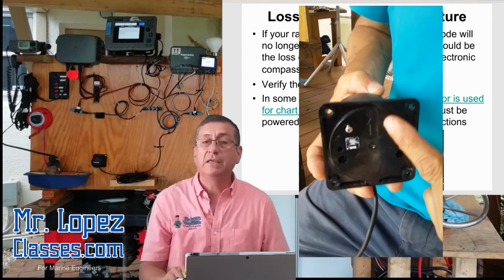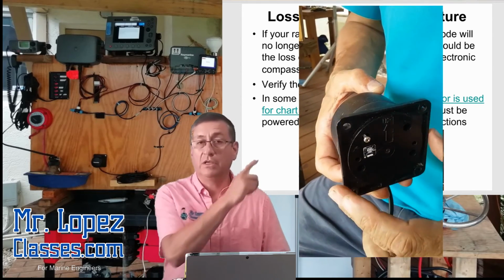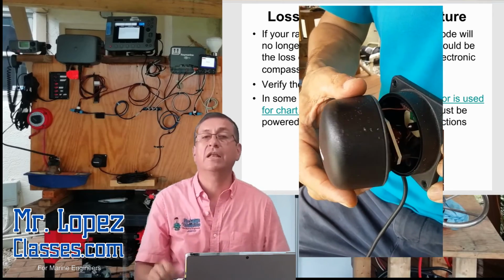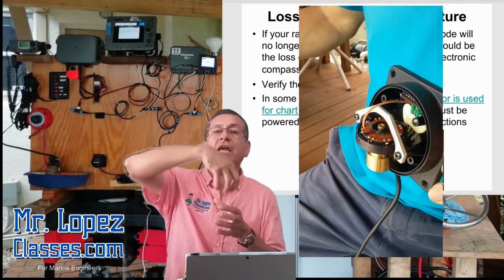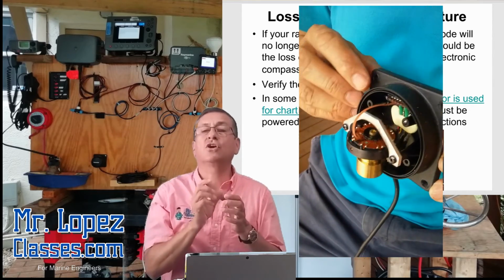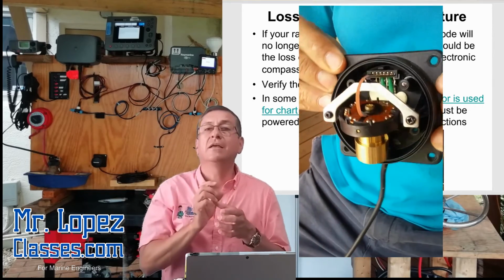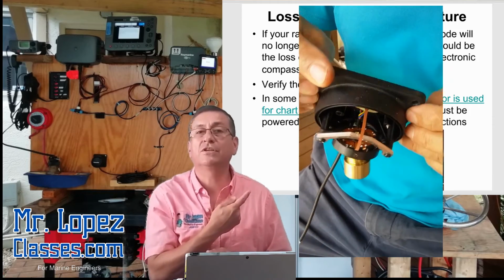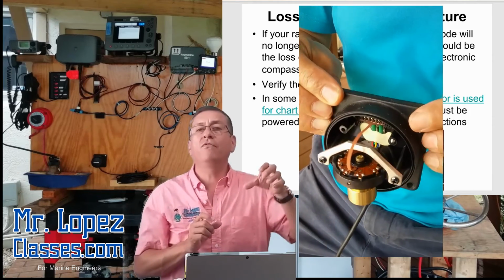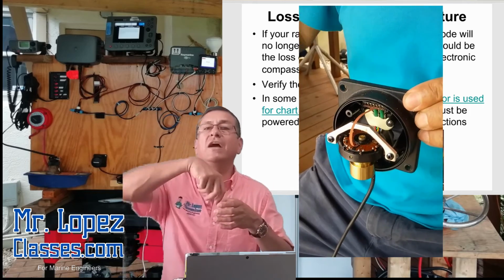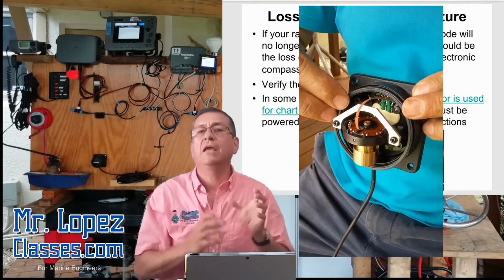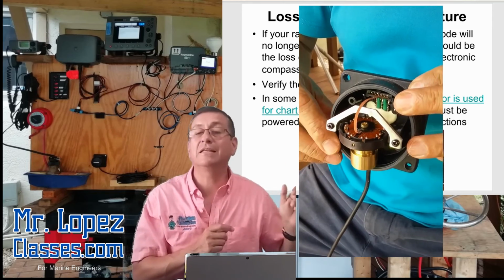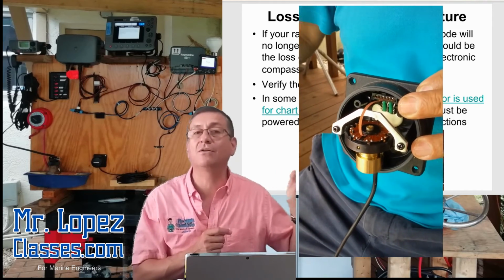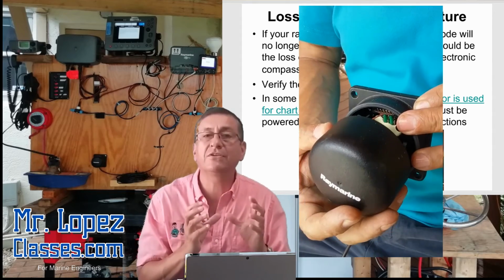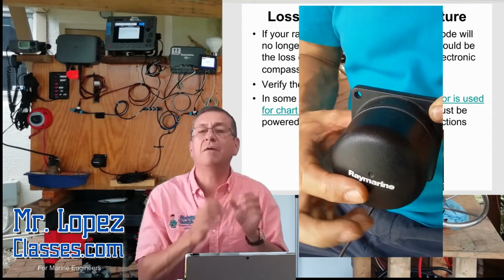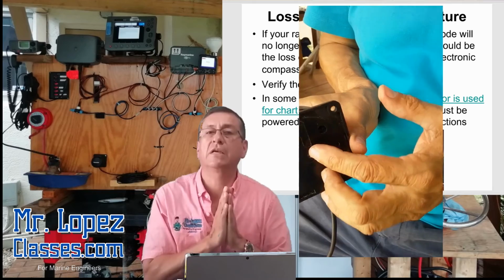If you open that sensor, that's the gyroscope you have on the screen right now. That gyroscope should be completely free. Verify by moving it with your hand and confirm it's free. Close it again, being careful with the seal, that gasket you see on screen. Put the cover back and verify the sensor is in a vertical position.